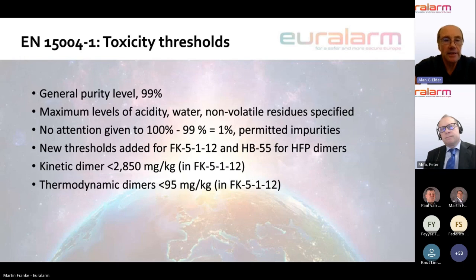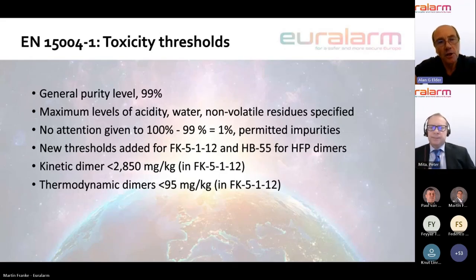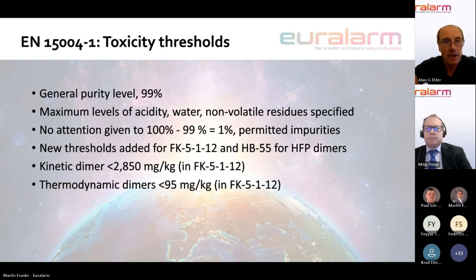The next subject is in respect to toxicity thresholds. So most people who would be familiar with the individual agent parts would be aware that the general purity level for the agents is 99%. It does vary, it can be 99.5, it's 99, but generally it's of that order, which permits around about a 1% impurity level for that agent still to perform and do its duty as a fire extinguishing agent. It does already specify within the standard what the maximum levels of acidity are, water and non-volatile residues. What it does not do is take account of what is permitted to be in the 1% of the impurities.